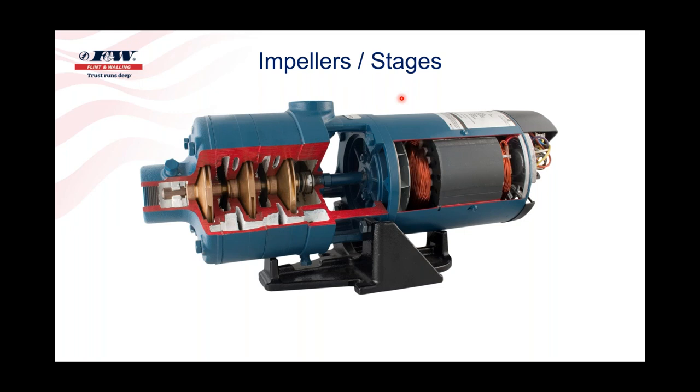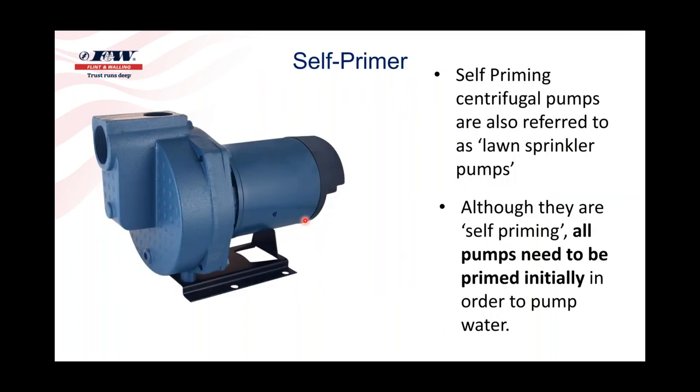He replaced all those pumps, and he never had to go back out on a single pump due to any type of impeller damage at all. So I suppose there are times where a bronze impeller might have some advantages over a plastic.